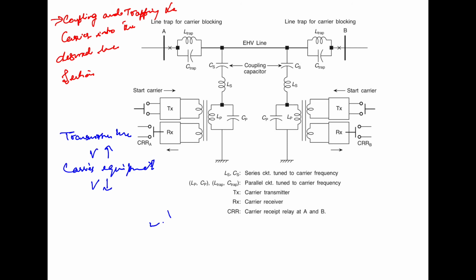Therefore, we need a method of coupling the two so that neither the high voltage line gets shorted through the carrier equipment, nor does the signaling equipment get damaged due to the extra high voltage. So we need a system in which the transmission line is not shorted by the carrier and signaling equipment, and the equipment is not damaged by the high voltage. Here in this figure is one arrangement for coupling the carrier on the line to ground basis.